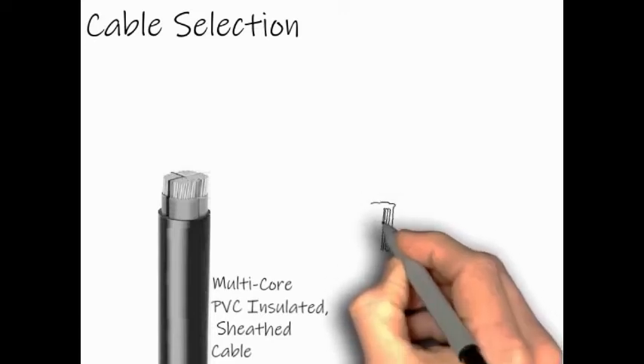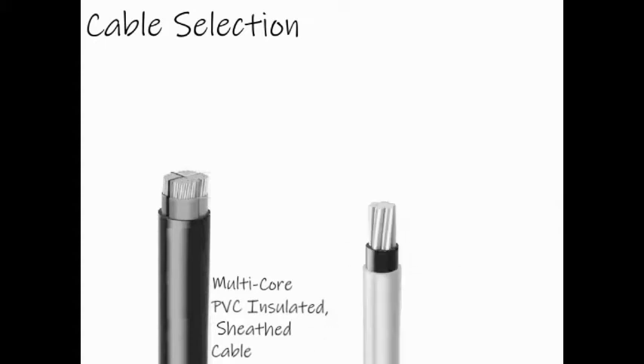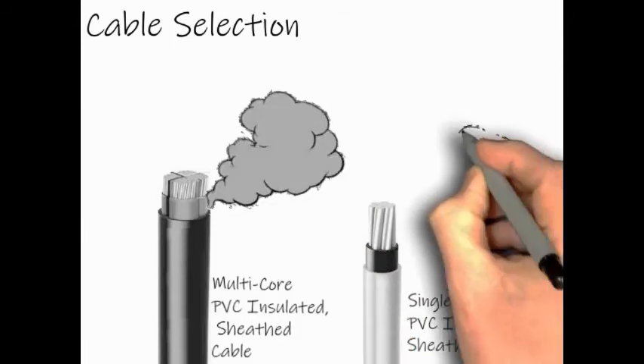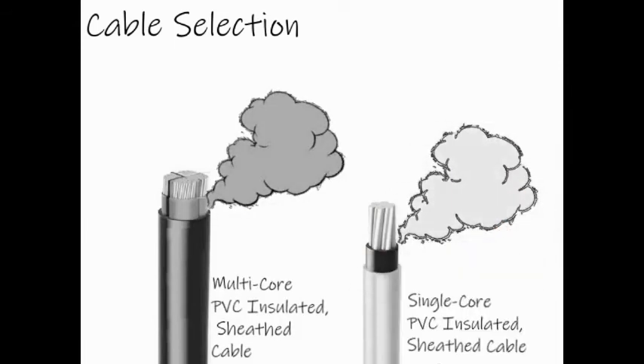In the next illustration, it shows a cross-sectional area. Let's take for instance, a single-core PVC insulated sheathed cable. A single-core conductor with a very large cross-sectional area enables more currents to flow. That is why during a design phase, it is important to consider if the intended load is meant for a single-phase circuit or a three-phase circuit. The insulation of the cable has a temperature limit as well. If the cable experiences high current, the heat generated will melt the insulation and this can lead to shorting among the copper core.